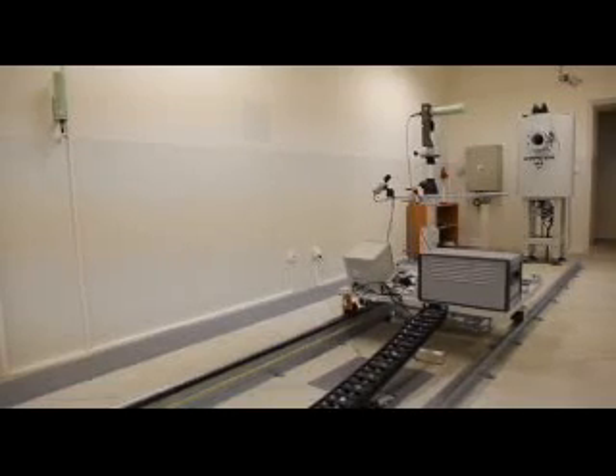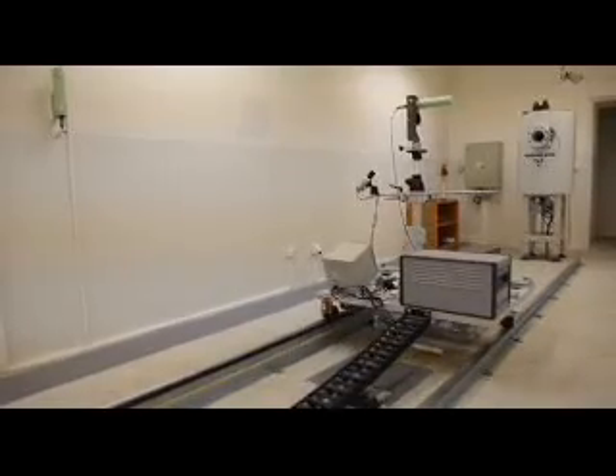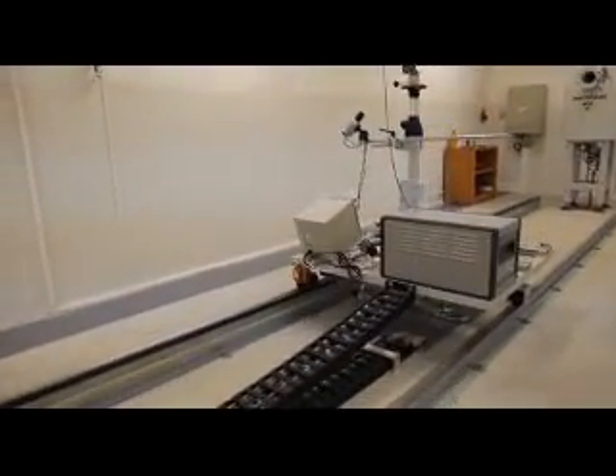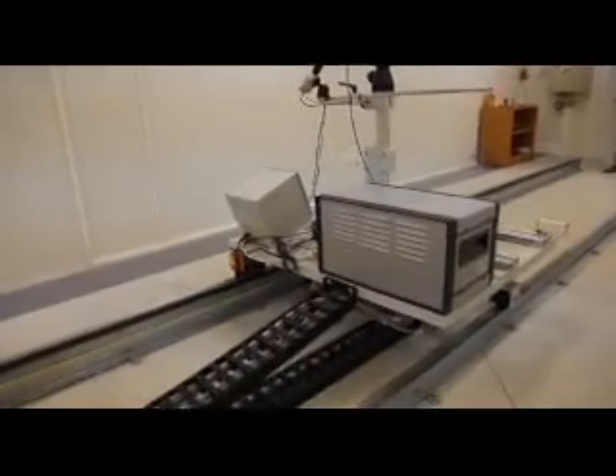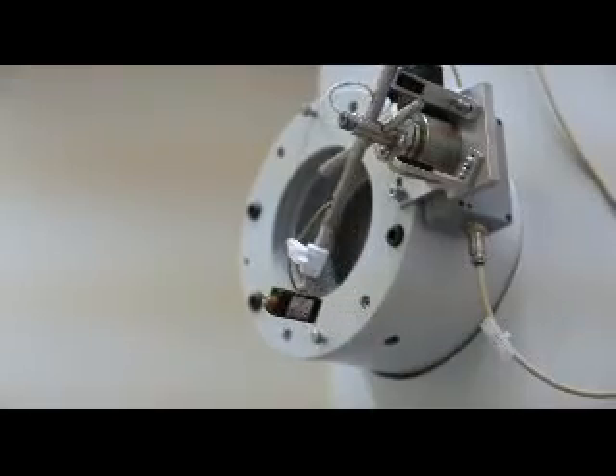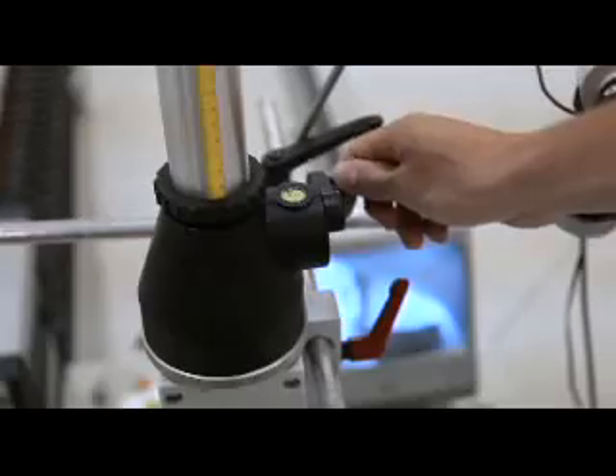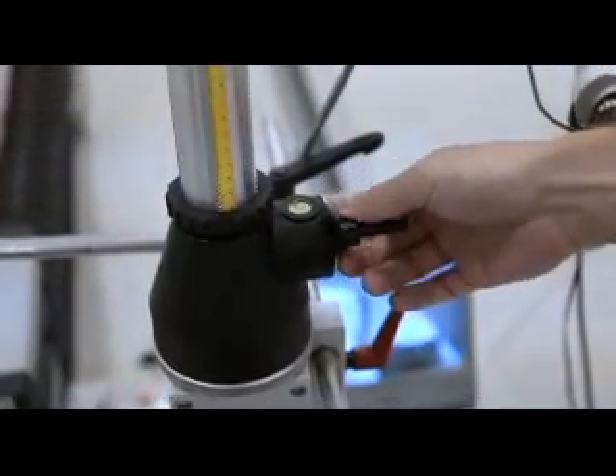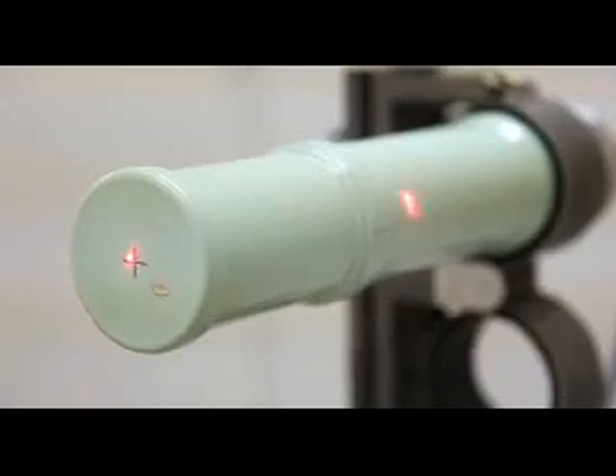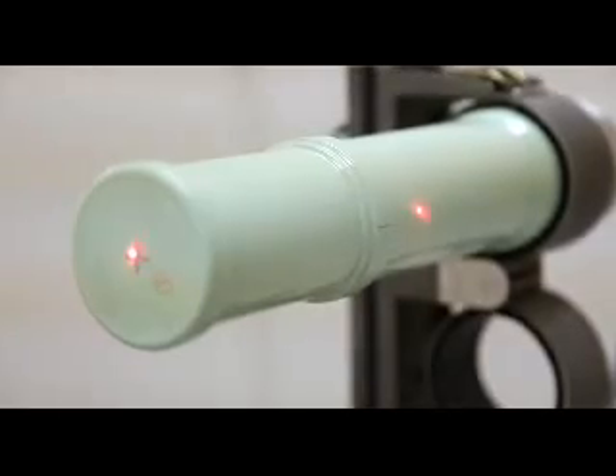The instrument being calibrated is attached to the calibration bench, which can move along the rails. This calibration bench enables the accurate setting of the distance between the detector and irradiator using an absolute position sensor, calibrated measurement scales, and a set of lasers.